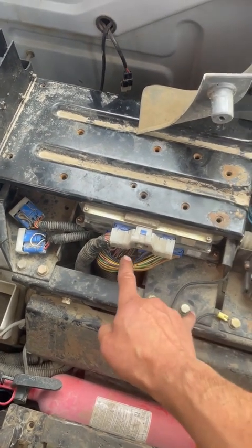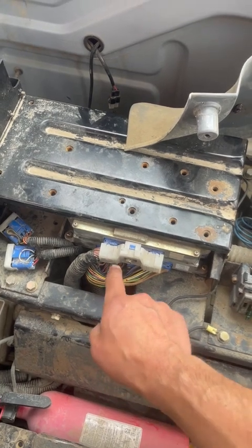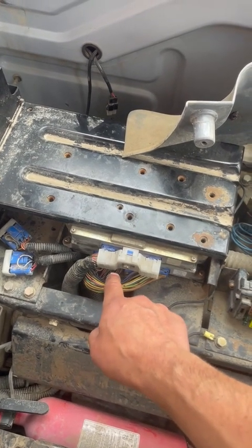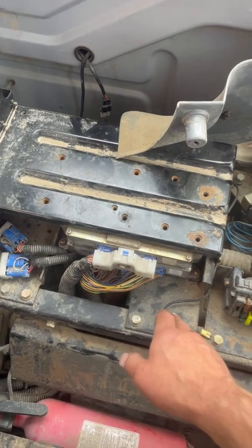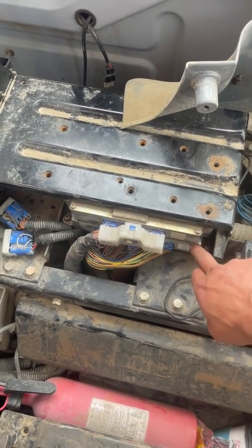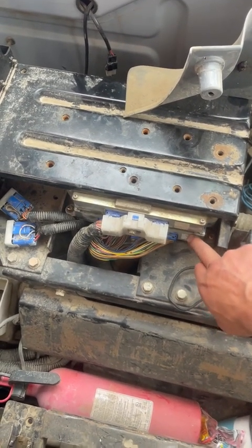and in the cab here with my light I could put my light on there and I could watch my voltage drop from 24 down to 0 and I would get nothing on the light. So now I've determined the issue is in fact inside the controller. So you're talking in the span of about 15 minutes, I've verified with my laptop the controller is trying to do what it's supposed to do. My wiring is good, but I'm not getting the correct current out of the controller to the solenoid.